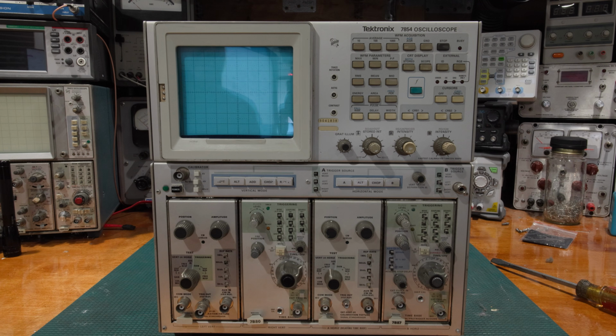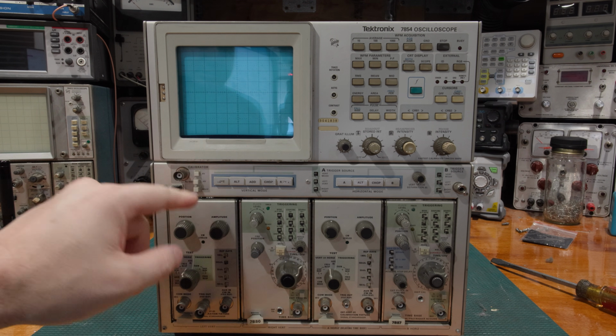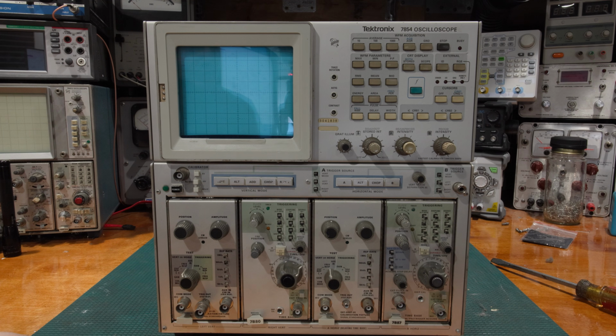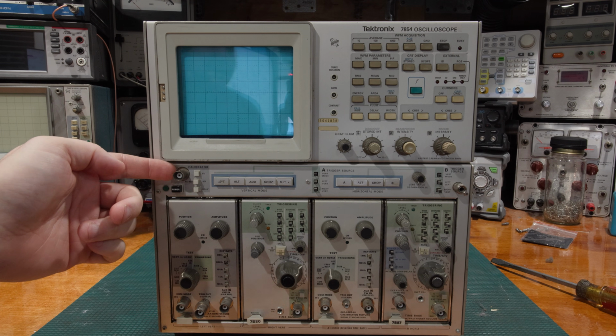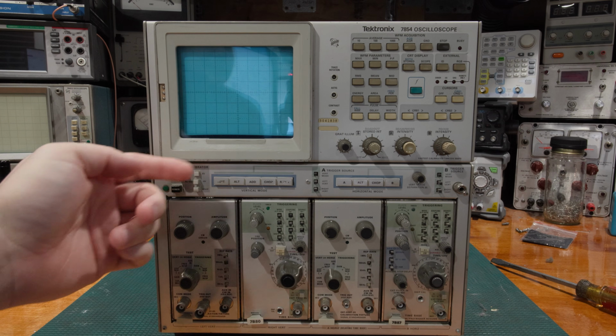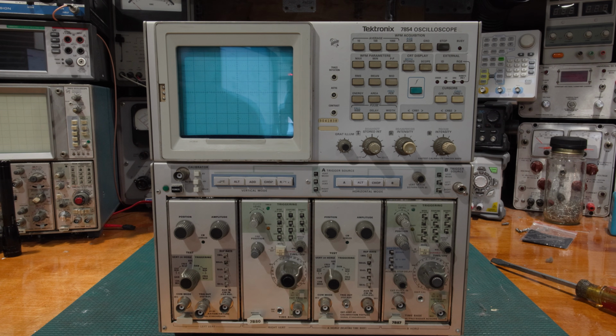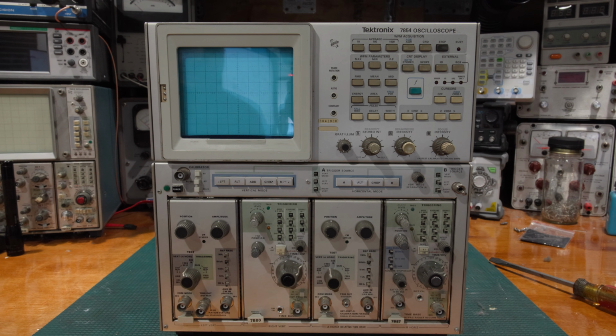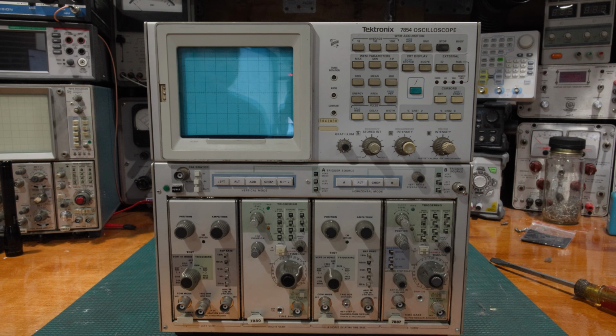The calibrator can be very rapidly checked with a modern scope. Do the waveforms look right? Are the voltages right? Are the edges good? Now, it does have a pretty fast edge coming out of the calibrator, so some of the slower scopes may struggle reading it directly. I've got some gigahertz stuff here in the lab. We can just pump it in and take a look at the fast edge, see if it needs to be adjusted. Frequency-wise, a frequency counter these days makes short work of it.